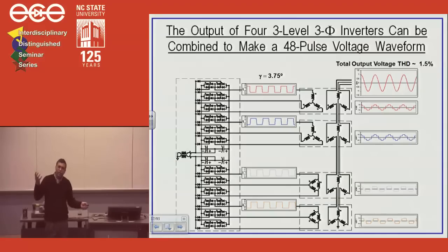It's a 100 MVA transformer or 200 MVA transformer. The magnetizing current is less than 0.1% of the load current, which means that if I make any error in my switching or any DC volt seconds into my transformer, I'm going to instantly saturate my transformer. What's the solution? Not to make that error, right?